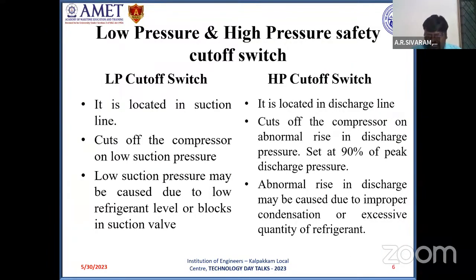And these are the two switches that are normally present at the compressor inlet and outlet: the low pressure safety cutoff switch and the high pressure safety cutoff switch. The low pressure safety cutoff switch is normally situated at the suction line, that is, at the compressor inlet line. So when suction pressure drops beyond a certain range, there won't be any proper circulation of refrigerant, or the working fluid present in the system may not be sufficient to give the required cooling effect. So generally, when suction pressure drops beyond a certain range, the low pressure safety cutoff switch trips the compressor, that is, stops the compressor.